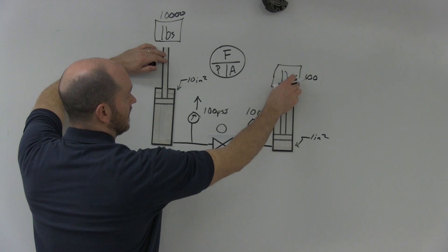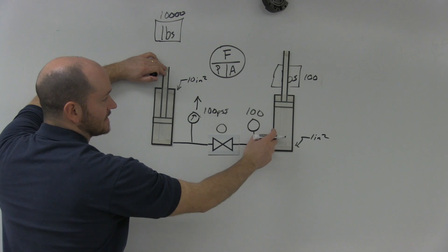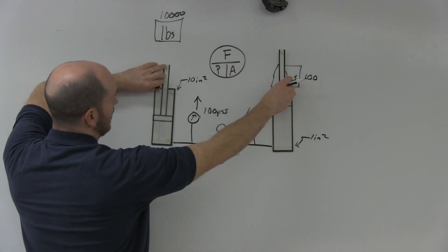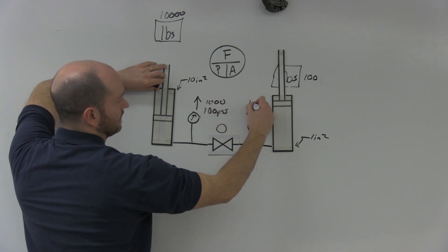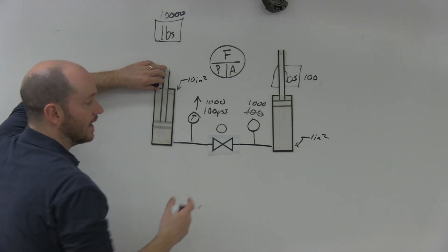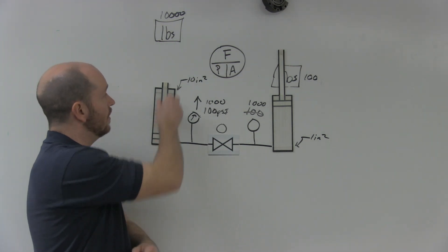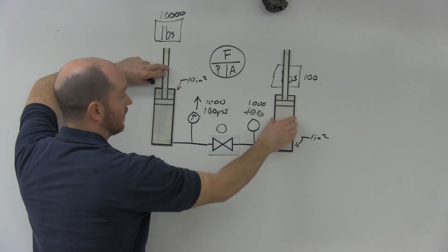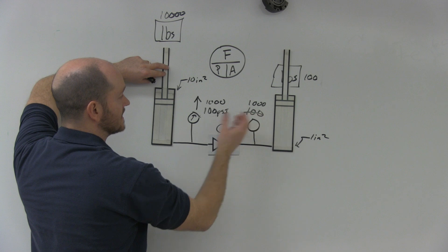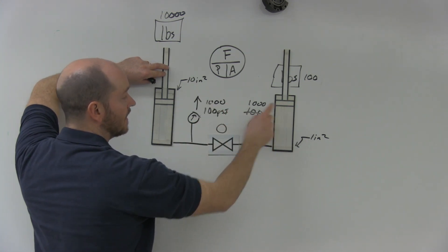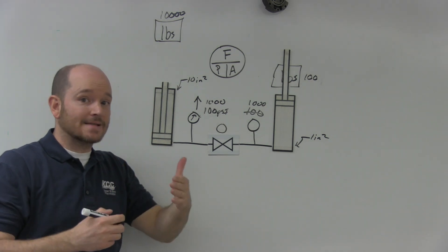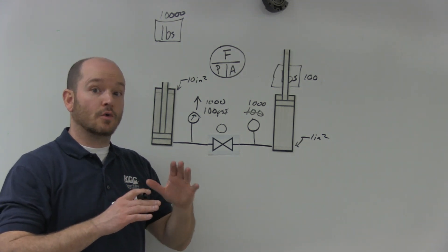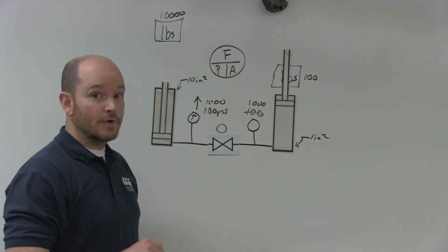Now let's say this cylinder has a shorter stroke. As soon as it gets to the top and flow stops, my pressure will go up to 1,000 PSI. In these circuits, if there's no flow you get maximum pressure, but if flow is capable because there's a load that can be overcome, flow will happen and pressure will be set by the load. Flow has to happen in a hydraulic system — it's the stuff that does stuff.